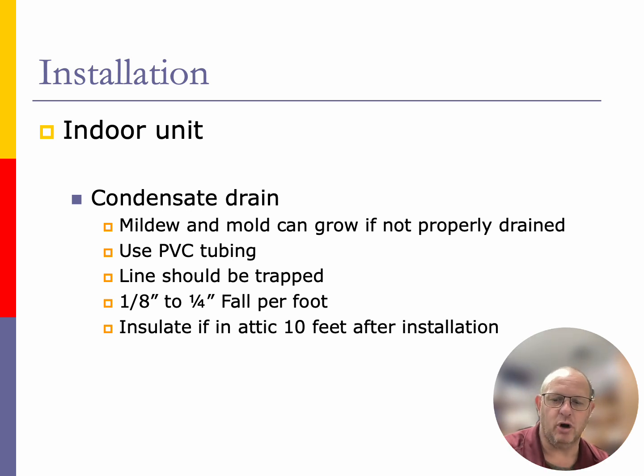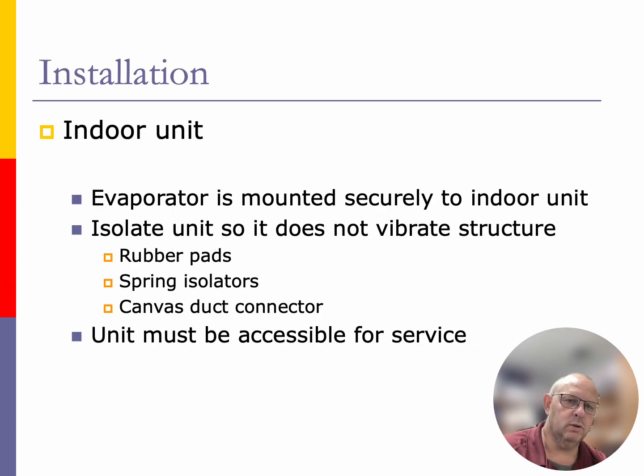The indoor unit, the evaporator, is mounted securely inside of that unit. We're going to try to isolate that unit from any of the structure with rubber pads, spring isolators, and canvas duct connectors, trying to break down the vibration coming off of it so our customers don't hear that particular unit running, especially when those fans get a little dirty and the blower wheel becomes unbalanced.